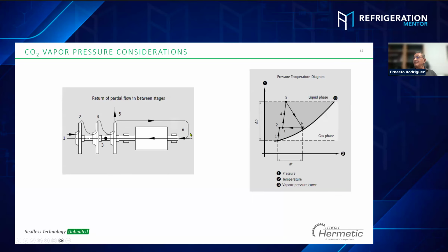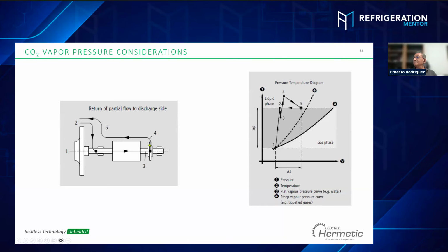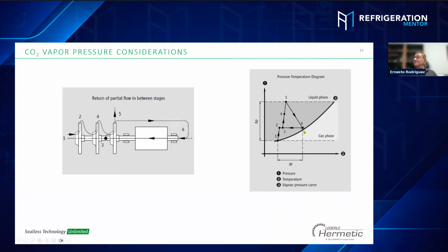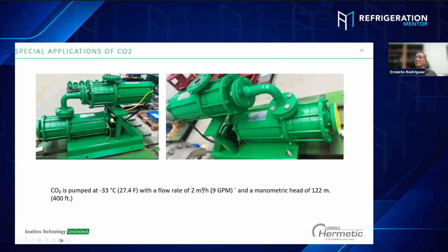Multi-stage is better for CO2 application versus single stage. You see, we have those high pressure peaks in the single stage. The multi-stage is more stable. The curve is more stable, preventing gas or flash gas from building inside the pump.